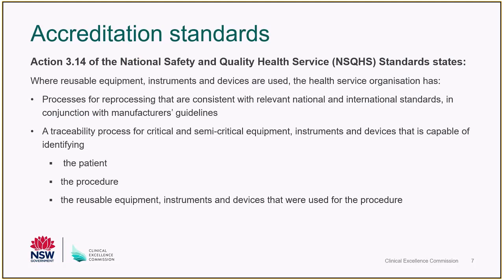So let's have a look at accreditation. Within the national accreditation, Action 3.14 of the national standards is very specific: where reusable equipment, instruments and devices are used, the health service organisation has to have processes for reprocessing that are consistent with relevant national and international standards, and in conjunction with the manufacturer's guidelines or recommendations. You also need a traceability process for critical and semi-critical equipment, instruments and devices that is capable of identifying the patient, the procedure, and the reusable equipment, instruments and devices used for the procedure.